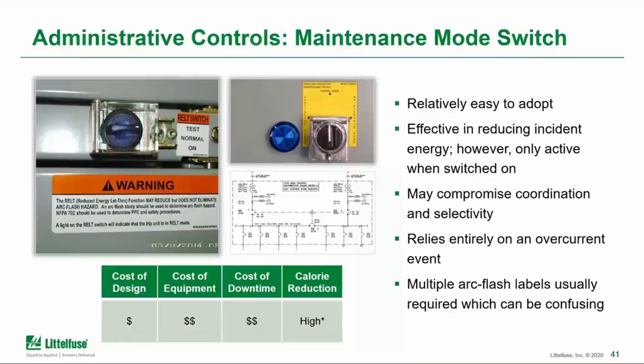And maintenance mode circuit breakers is also another popular method. This would be more of an administrative control rather than an engineering control, as it does require human effort to turn the maintenance mode switch on and off at different timing. So the cost of design is fairly low. It often just requires upgrading the type of breaker that you may already have in place.